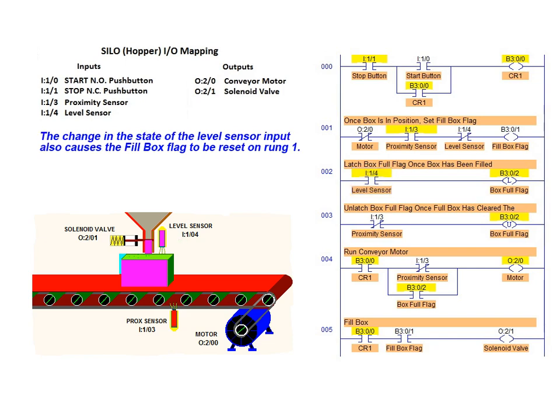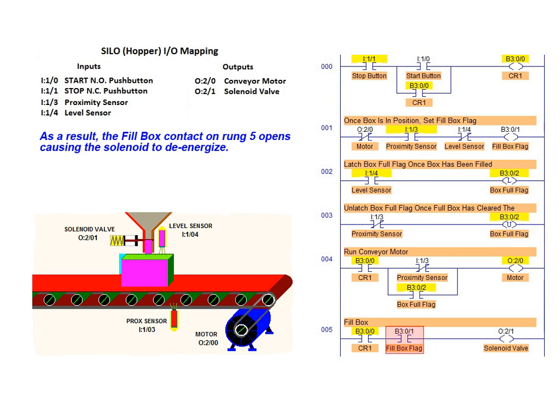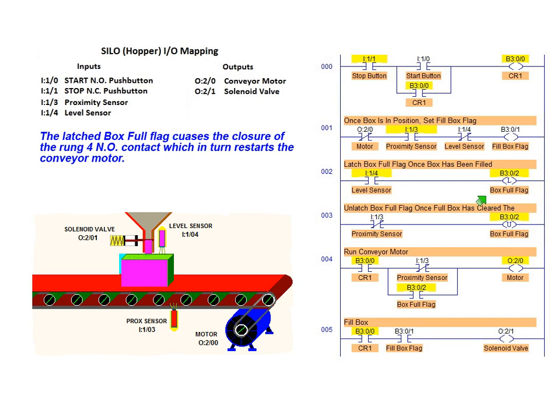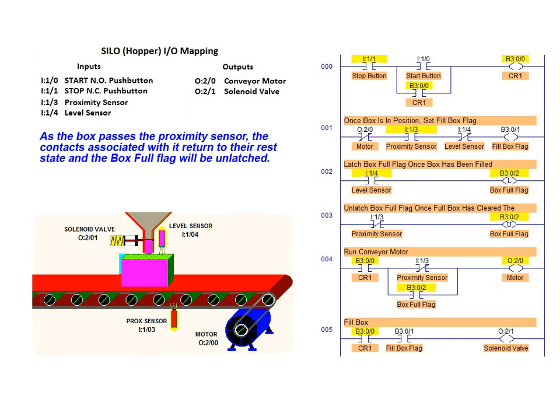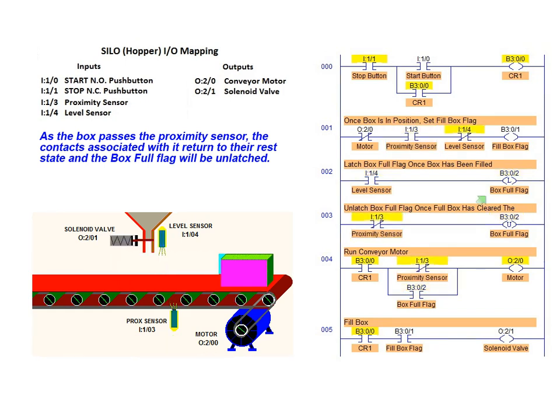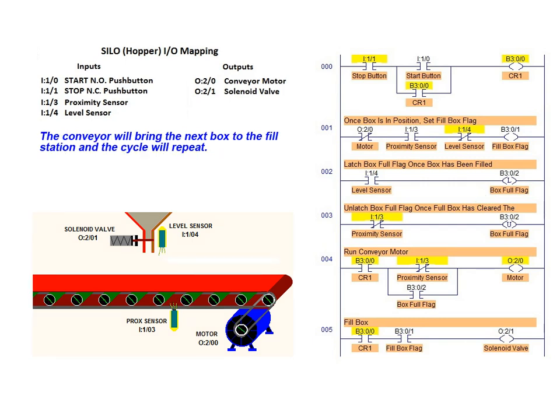This change in state of the level sensor input also causes the fill box flag to be reset on rung 1. As a result, the fill box contact on rung 5 opens, causing the solenoid to be de-energized. The latching of the box full flag causes the closure of the rung 4 NO contact, which in turn restarts the conveyor motor. As the box passes the proximity sensor, the contacts associated with it return to their rest state, and the box full flag is unlatched. The conveyor will now bring the next box to the fill station, and the entire cycle will be repeated.